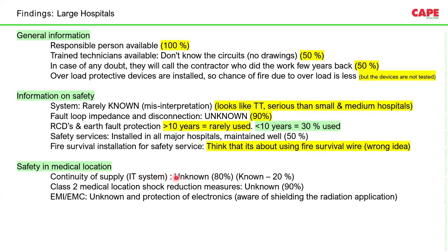Safety in medical location, continuity of IT supply: mostly it's unknown, 80%, and about 20% it is known. Class 2 medical location shock reduction measures are again unknown in 90% of cases. The shock reduction supplementary protective equipotential bonding is missing. In some hospitals, of course, rubber flooring is made, thinking that this may protect from shock, but most often in a conductive location, where conductive fluids are sometimes on the floor, it will be very difficult to achieve safety in that way. Of course, rubber or plastic flooring is required, but protective equipotential bonding is also required.